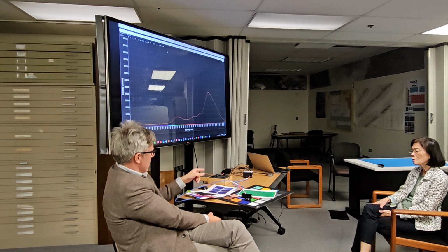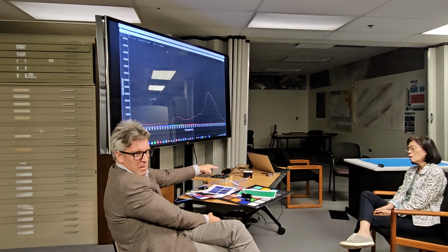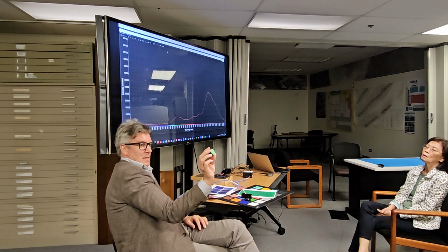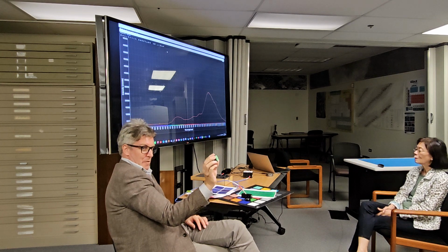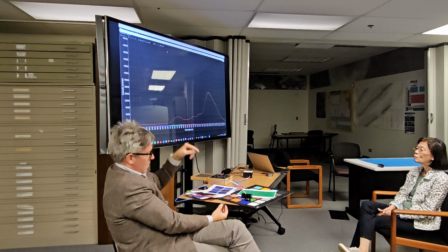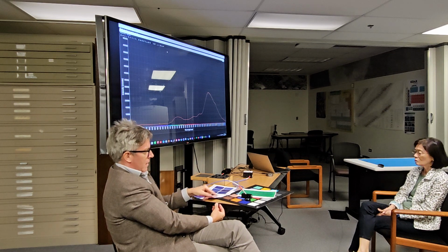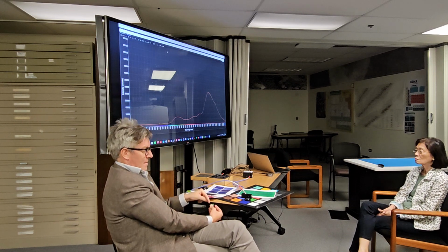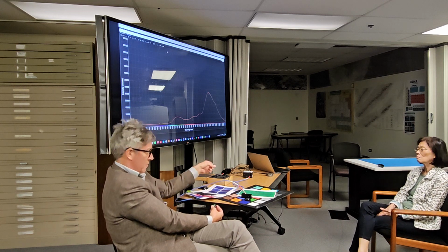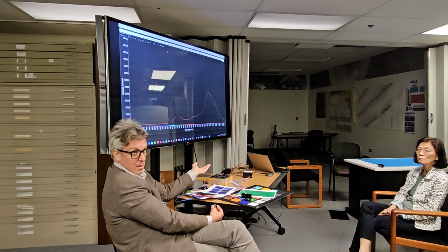Because here's another reason: if that spectrometer starts going a bit weird, if I point it at this and I know this isn't changing, then every measurement should be kind of the same, plus or minus the noise, right? But if I point at this on day 1 and I get a spectrum, and then I point at this on day 100 and I get a different spectrum, which is outside of the noise, then I know there's a problem with my spectrometer, right?